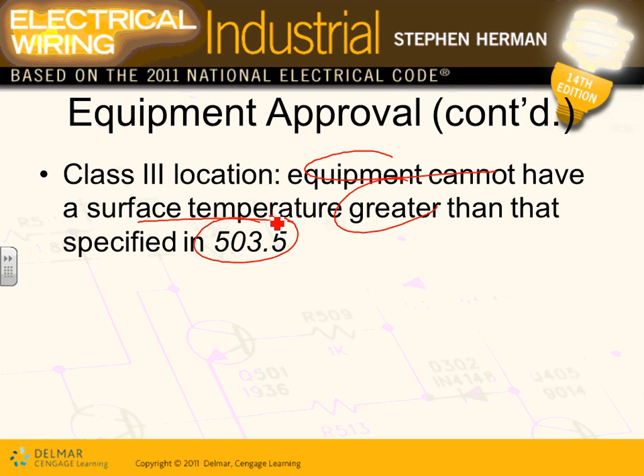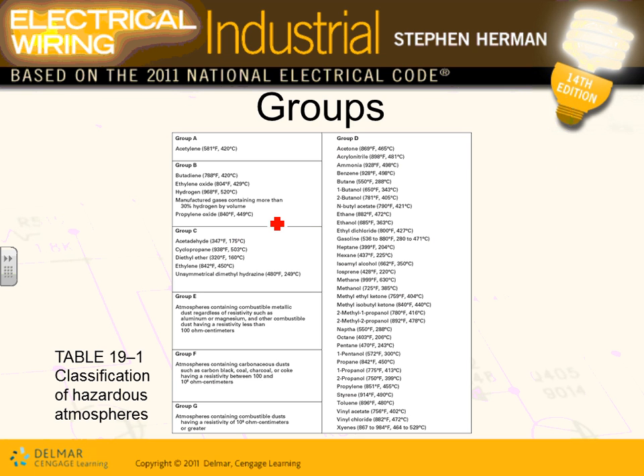No. So the whole idea, guys, class 1, 2, and 3, is to minimize igniting the flammable, combustible, or ignitable gases, vapors, or dust in these areas by controlling the temperature. How do you ignite things? Either by giving them a spark or by giving them a higher temperature, right? So they're going to starve these hazardous locations of ignition sources. Any comments, guys? Any questions about the equipment? So when you put equipment in these areas, in the back of your mind, you have to starve the source of ignition by sealing the sparks and by not allowing the temperature to increase. Okay.